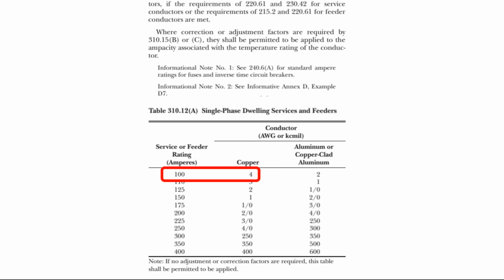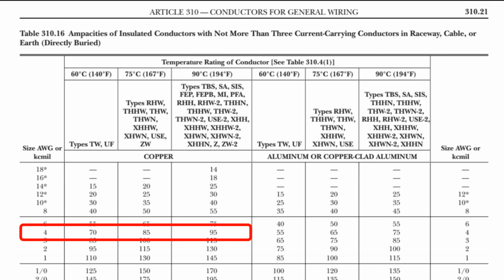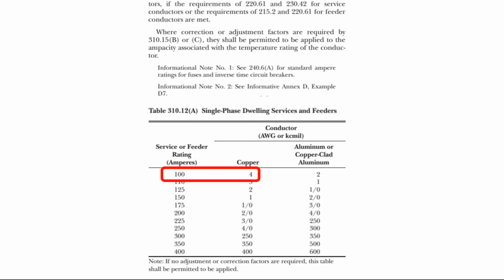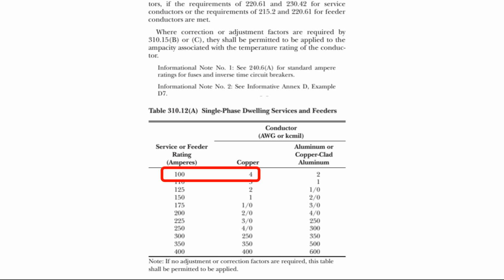310.12 says a number 4 AWG copper conductor is okay on a 100 amp 3-wire dwelling service or feeder. Number 4 is only 95 amps capacity. The reason 310.12 says a number 4 AWG copper conductor is okay for a 100 amp dwelling feeder is that demand factors are already pre-estimated for a single unit dwelling. Number 4 is okay for 100 amps, for the same reason number 2 is okay for 125 amps. That number 2 feeder will never actually see 125 amps. In fact, in a course I took at a utility company, the engineer teaching the class said the average 200 amp service is running at less than 60 amps 90% of the time. So there's a lot of overhead built into these provisions.